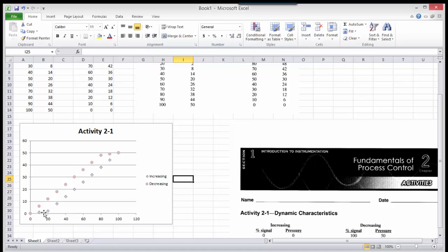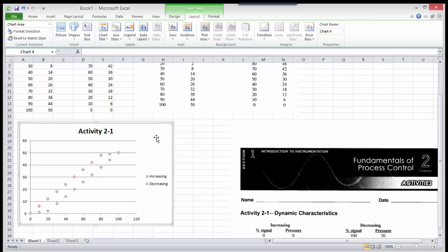So here's the dead zone, and then you can see a more or less region of linear response from about 20 or 30% all the way up to 100%. Then as we start to decrease, another dead zone. Well, here we're telling it to reduce, and it's not really reducing until we get clear down here to 80%. Then it's linear all the way down to 0.